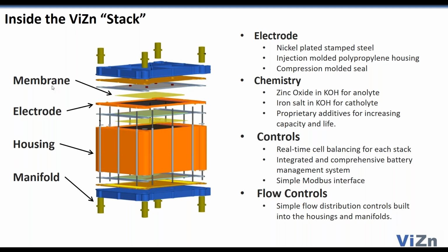Key things in the system are controls—we do real-time balancing in the stack. The control package is a box on the side, not shown in this exploded picture. We have an integrated battery management system in every stack and for the entire container, with a simple Modbus interface out to the real world for plant-level control packages and for interfacing with the inverter.